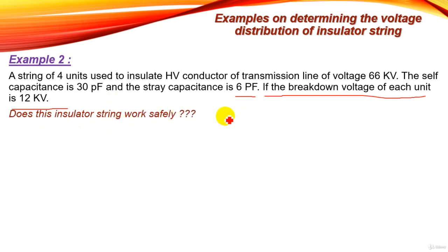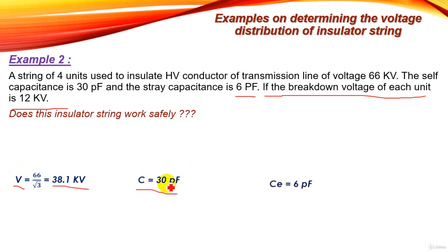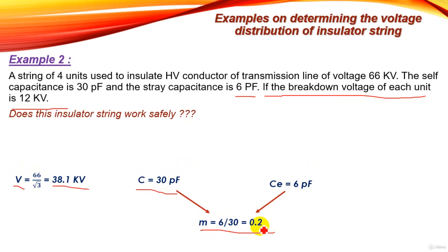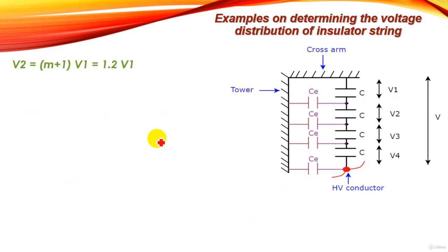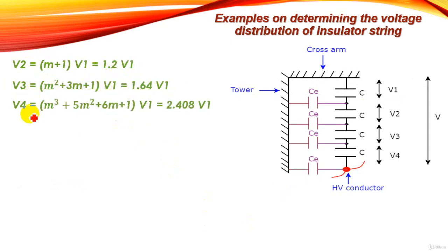The phase voltage is 66 over root 3, which equals 38.1 kilovolt. Self-capacitance is 30 pF and stray capacitance is 6 pF, so m equals 6 over 30, giving m equals 0.2. The voltage distribution equations become: V2 equals 1.2·V1, V3 equals 1.64·V1, and V4 equals 2.408·V1.